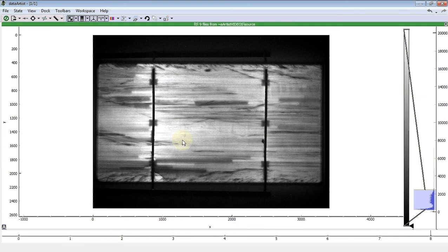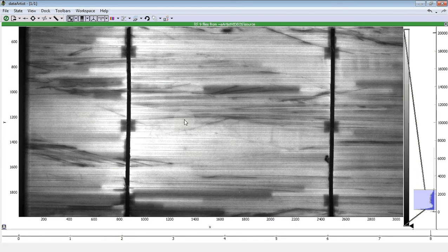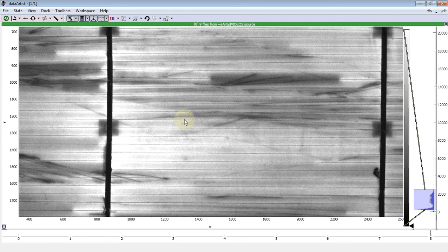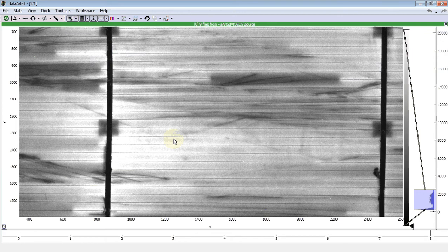The question is, which of these images is already good enough? I'm speaking about noise. When is an image good enough? I mean, we could of course wait longer. The last image was taken, if I look here, at 60 seconds. Is 60 seconds already enough, or do we maybe need 2 minutes or 3 minutes in order to have a good image? Currently, the EL standard from the IEC says we should have a signal-to-noise ratio of 45 as absolute signal-to-noise ratio, so the signal should be 45 times higher than the noise level.